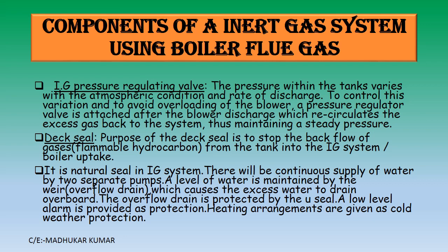The overflow drain is protected by the U seal. A low level alarm is also provided for the protection of the deck seal. Heating arrangements are given as cold weather protection. And in that we have the demisters also. So this is the functionality of the deck seal. In detail we are going to see in the diagrams.